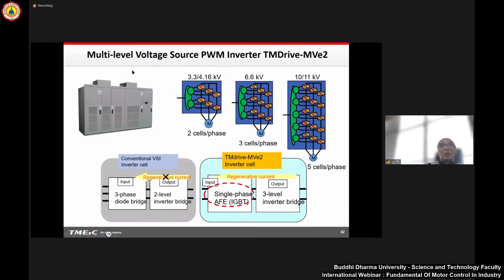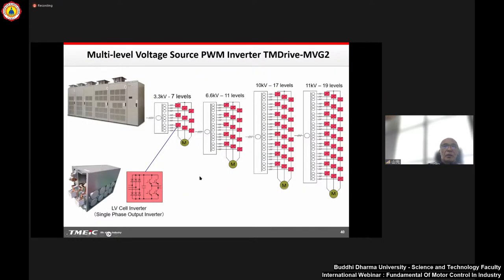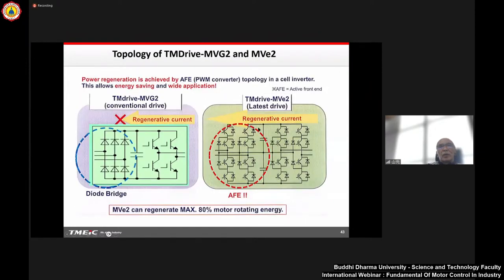This is the TM drive MVe2. The difference between this and the other MVG2 is in the inverter configuration. This MVG2 uses a single phase NPC converter section and single phase NPC output, like this. The difference is that while the other one is not able to control regenerative current from the motor back to the power supply, this one can regenerate using active front end technology. This is the major difference between this MVE2 and MVG2.